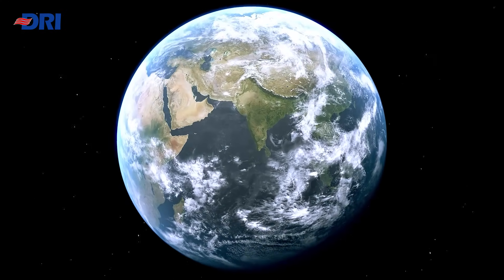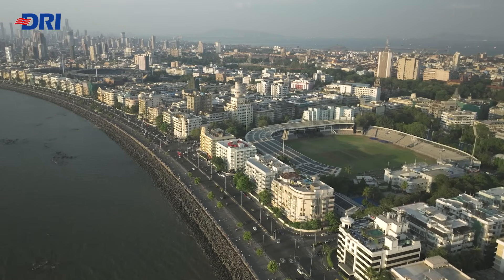Now consider a different climate like Mumbai, which experiences both high temperatures and elevated humidity levels. During peak summer, outdoor temperatures can reach 35–38°C with a maximum wet bulb temperature of around 26–28°C. Despite these challenging conditions, an IDEC system can still provide efficient cooling, reducing supply air temperatures to approximately 24–26°C. This represents a significant energy-saving alternative to traditional air conditioning systems, while maintaining indoor comfort even in humid climates.